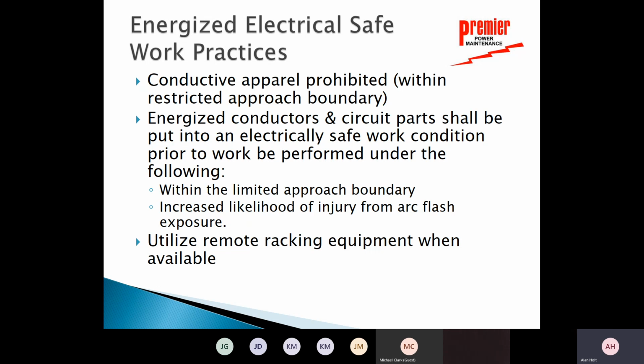within the limited approach boundary, where an unqualified person can be. Energized conductors and circuit parts shall be put into an electrically safe work condition prior to performing work. Basically, before you get any closer than the limited approach boundary to exposed, energized electrical parts and components, you need to make sure it's in a safe work condition. We want it shut off, tested dead, locked out, grounded.